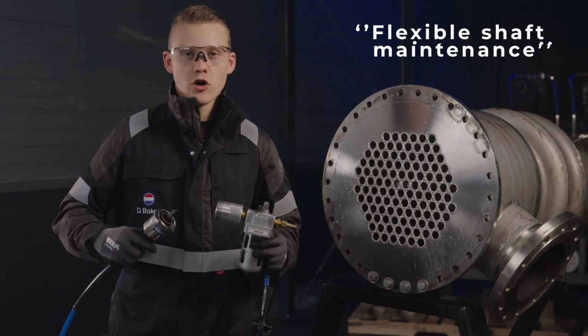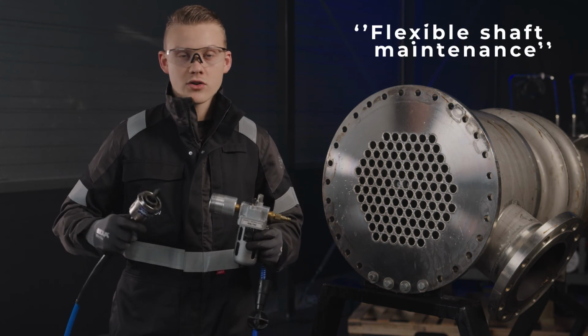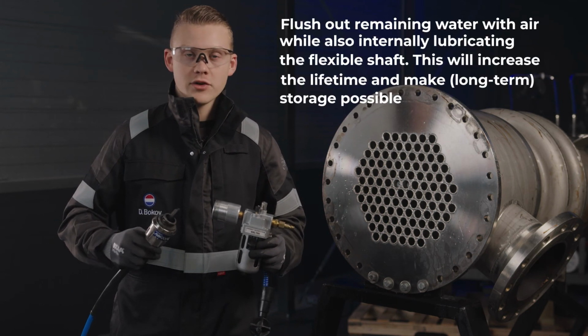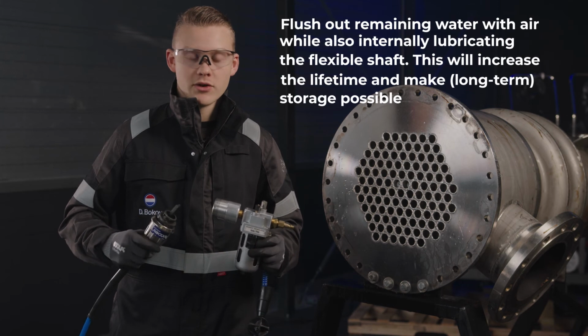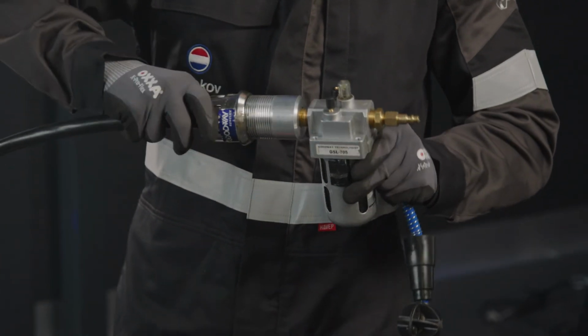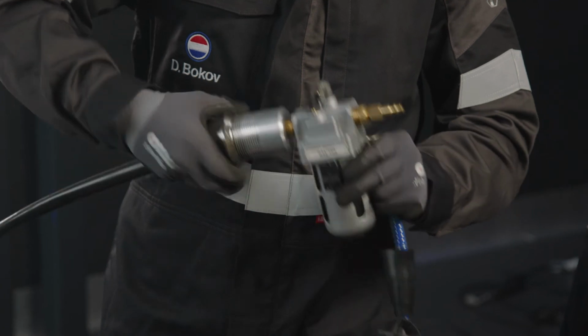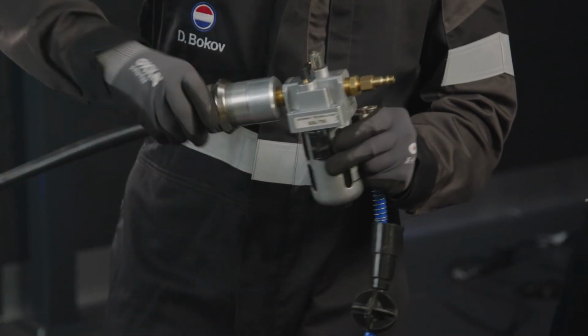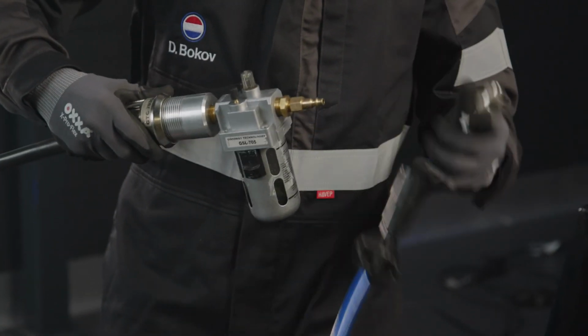After a wet cleaning, the shaft will always have some leftover water inside of it. This can cause corrosion and oxidation. Therefore, it is very important to flush this water out. Use the GSL 705 tool to connect the flexible shaft on the one side and compressed air on the other side.